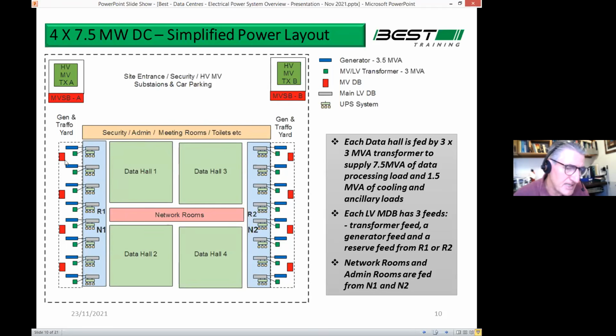The red box outside then is the MV switchgear, which feeds the transformers. These green boxes are supplied at 20 kV typically from the red switchboard here. And that module just repeats itself all the way around. So in this case, the basic building block is about a 3 MVA transformer and a 3 MVA generator feeding into a board. And that board in turn feeds down into the UPS system. And the UPS system in turn feeds power to the server. Well, not directly. There's a whole series of other equipment that it feeds through before it gets to the servers, but that's where the servers draw their power from.